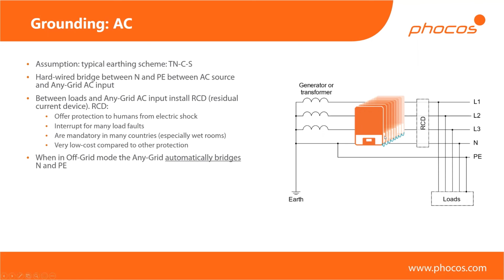In this kind of scenario, to protect people, the actual users, from electric shock, you would use a residual current device, an RCD. And in order for that to work, there needs to be a connection between the neutral and the ground. If a typical off-grid inverter is working in off-grid mode, as I told you before, it disconnects neutral and line from the grid. So basically this bridge you have here between neutral and ground no longer exists, because the whole first part is basically cut out of the system.